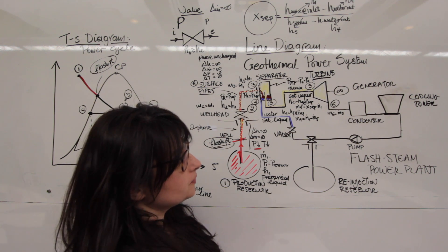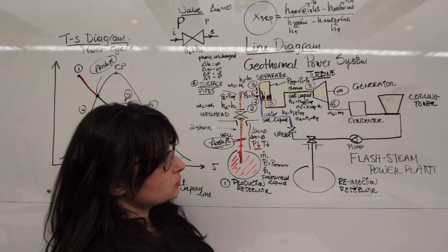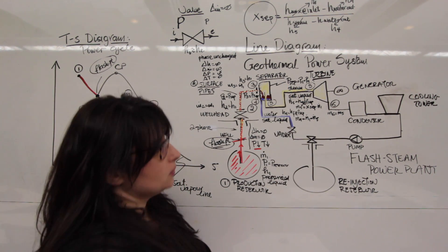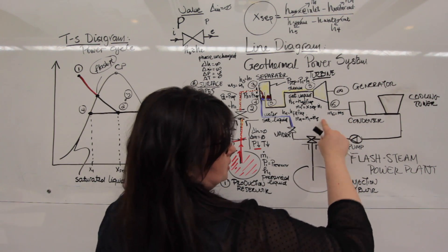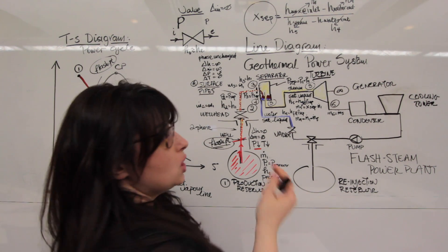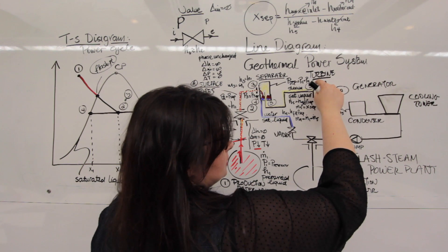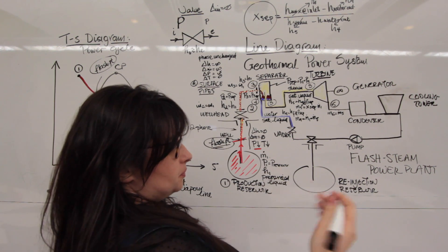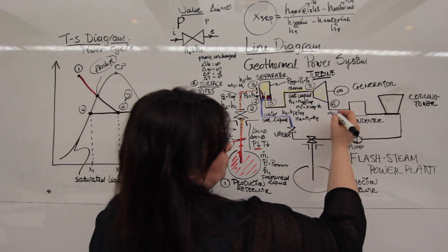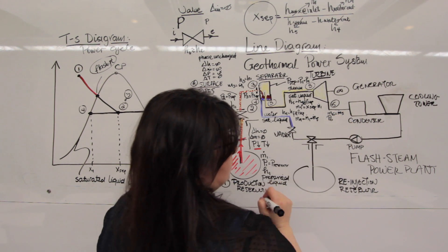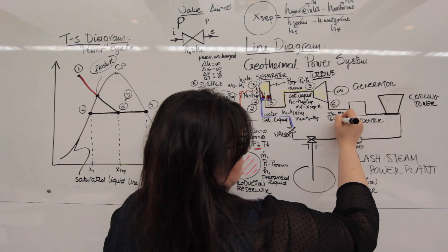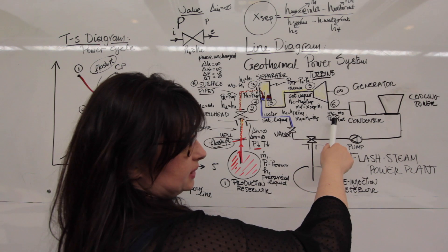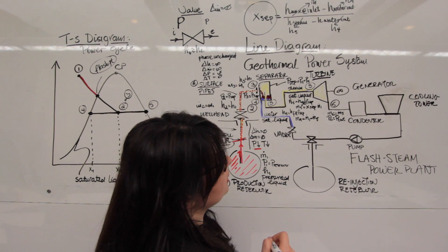The pressure at the turbine outlet is also set as a design condition, such as the pressure that we have for the separator, so it will be known to you. In the example we were talking about in the lab, it was at 0.1, while the pressure at the inlet — because it was defined by the separator — was equal to the separator pressure, which was at 7. So P6 is equal to P turbine outlet, and it's known. For the example, it was 0.1 bar absolute.